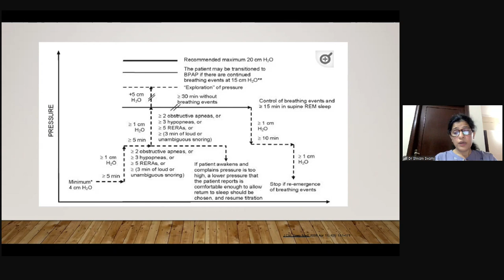I would also briefly like to discuss the BiPAP titration. So, if your subject is for a BiPAP, then again, in the middle of the night, you switch over to a BiPAP with a minimum IPAP of 8, a minimum EPAP of 4, and you increase the EPAP and IPAP both by 1 centimeter of water for apneas. And if there are other events like hypopneas, RERAs, or snoring, just increase the IPAP by 1 centimeter. And we follow the same protocol that we look for these events every 5 minutes until these events are eliminated for at least 30 minutes without events, with at least 15 minutes of supine REM sleep.